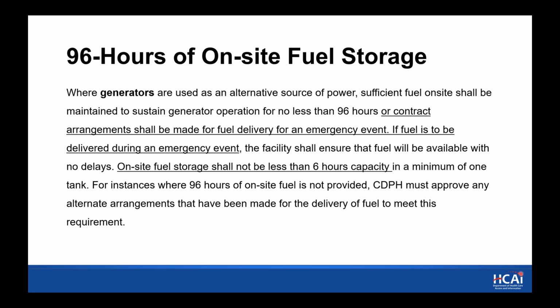And then we've added this piece that on-site fuel storage shall not be less than 6 hours capacity. So 6 hours on-site and either the 90 hours additionally on-site to get you to 96 hours, or if an acceptable approach for delivery, you can have 6 hours of fuel on-site and 90 hours delivered. CDPH will need to approve any alternate arrangements that have been made for delivery of fuel to meet this requirement.